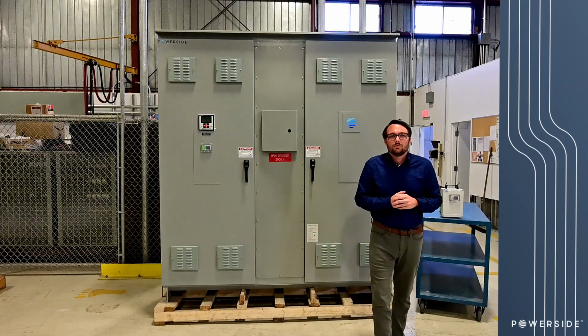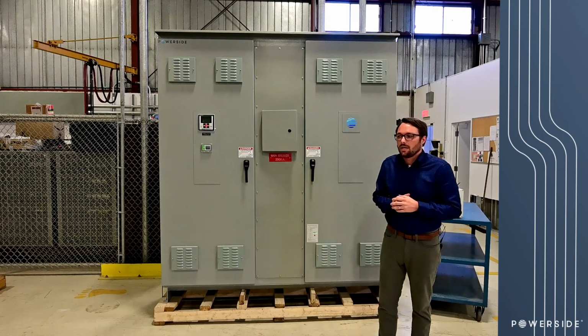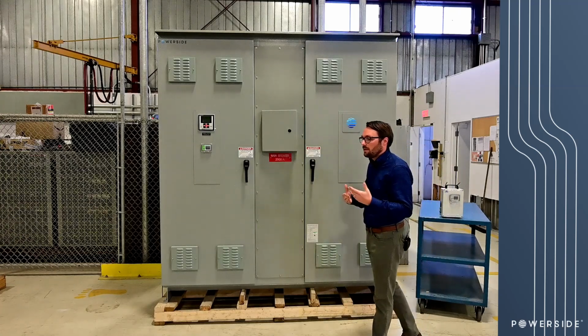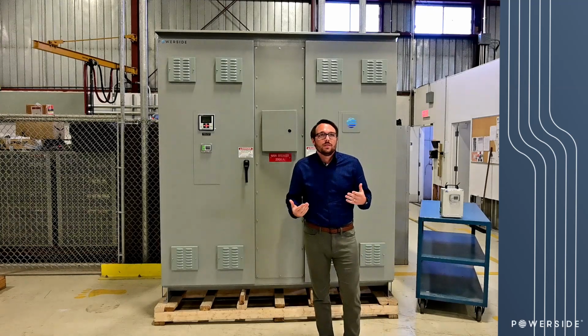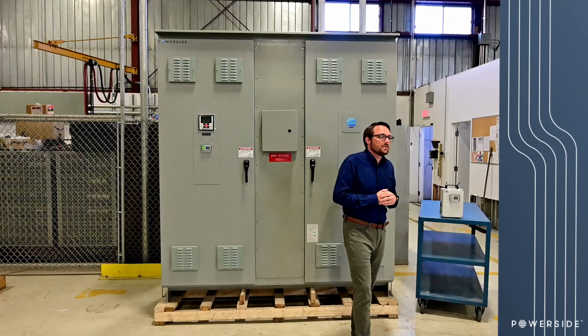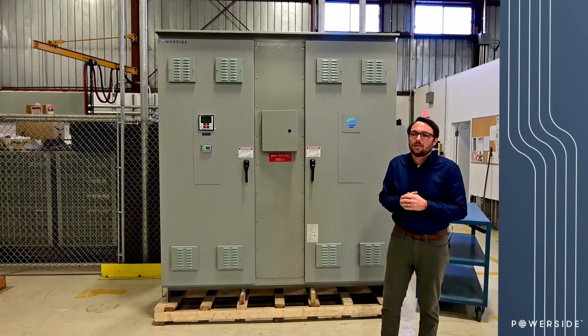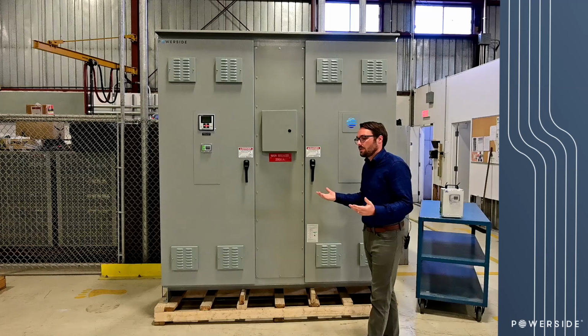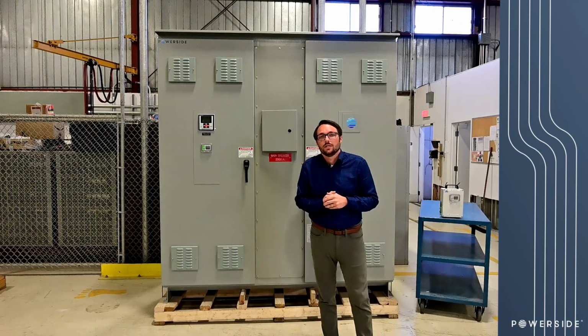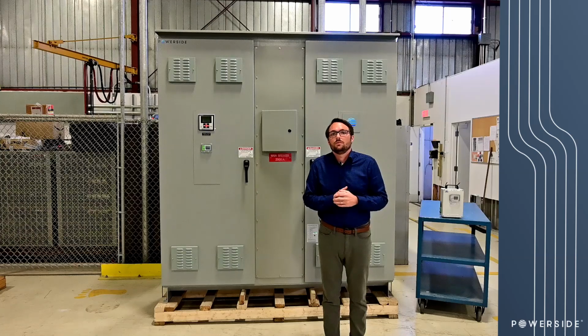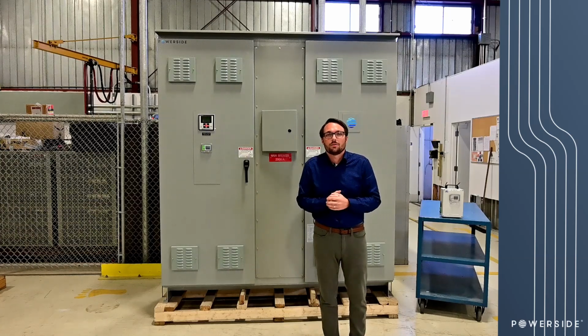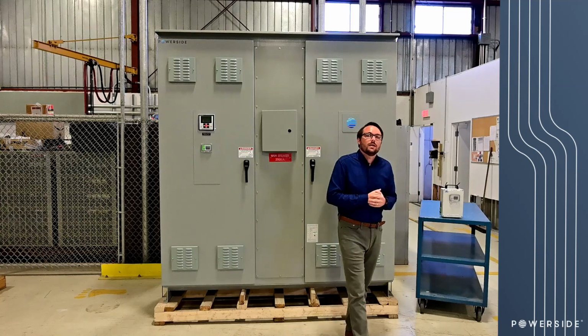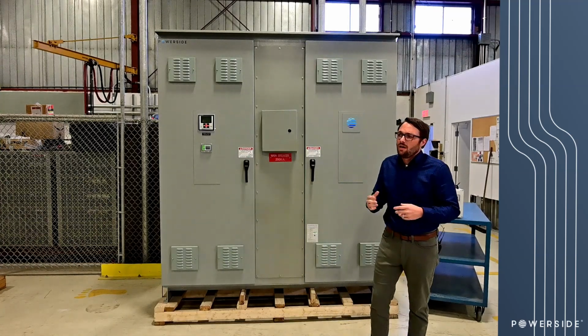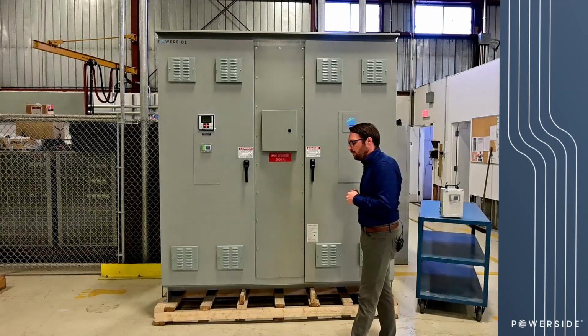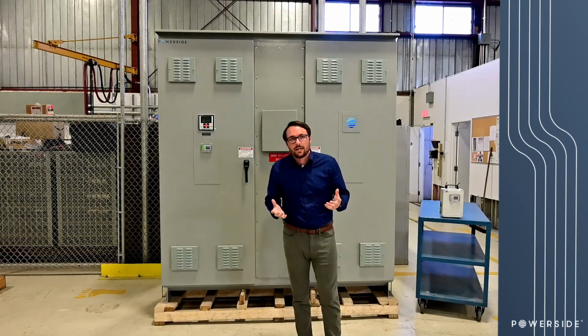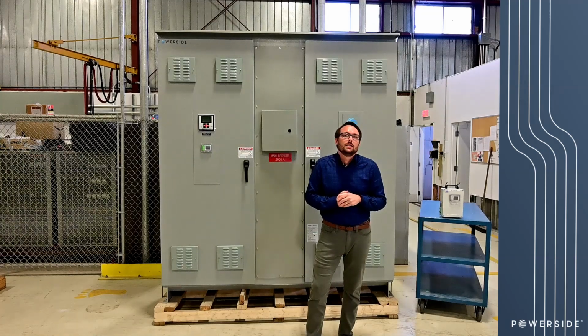One of the unique things about the utility that was serving power to this client is that they have a power factor requirement of 95%. Now, this is certainly on the high side of what we see. 90% is very common. And then, of course, on the other side, we have some clients that are KVA billed. And with KVA billing, you need to maintain a unity power factor or a perfect power factor, or you're paying for that waste. So when this client came to us, we went through and did electricity bill analysis to determine what they needed for correction.